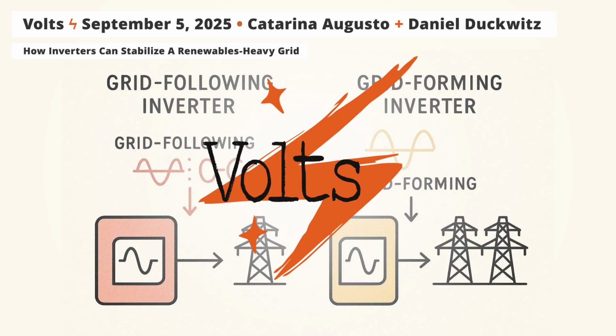I'm sure there are areas in the US too, in California, Texas, and elsewhere, with really high renewable generation. As a system operator, ISO, or utility, you wouldn't build any more transmission lines than you absolutely need to feed the power. We don't even build the transmission lines we do need. So you end up operating the transmission line very close to its limits, and that makes it a weak grid area.